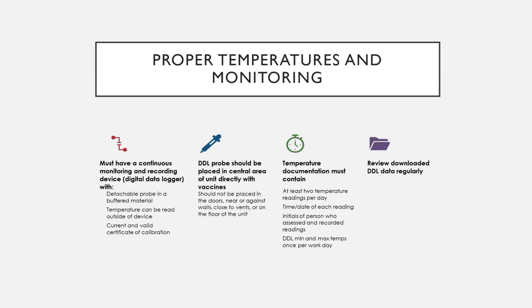What is calibrated is the probe. So if you're going to change out your DDL with the new one, we've noticed that people will just leave the probe and change out the monitor, but it's actually the probe that is calibrated. So if you're going to change out your DDL, change out the whole thing, the probe as well as the face, the monitor. DDL probes should be placed in the central area of the unit directly with vaccines. They should not be placed near the doors, against the walls, close to vents, or on the floor of the unit.